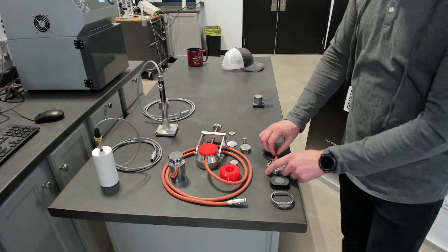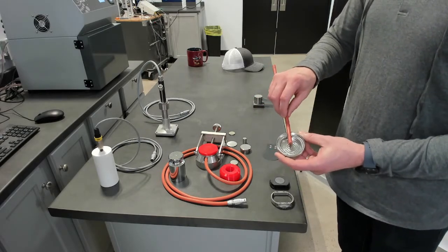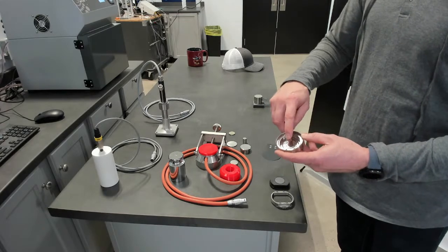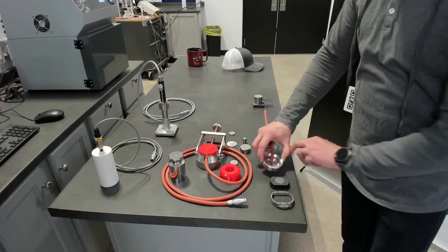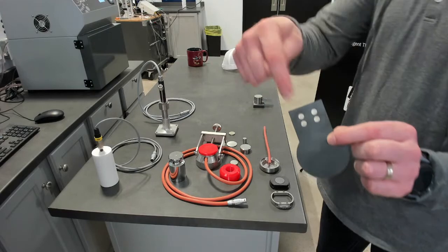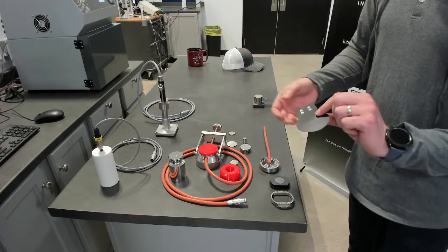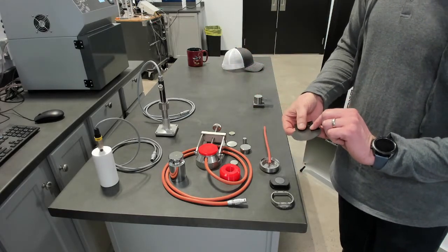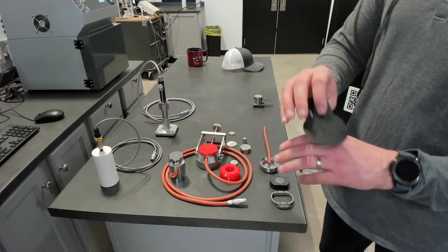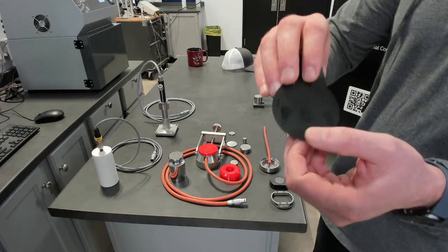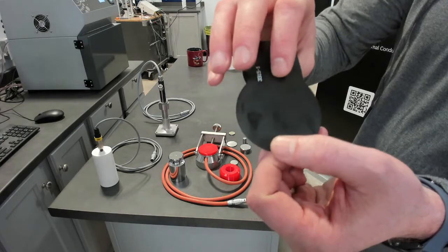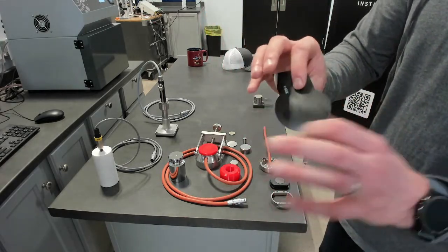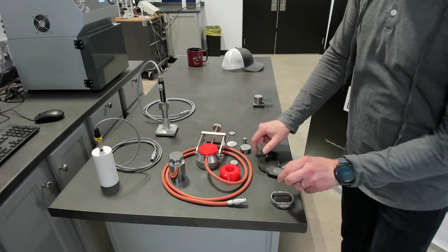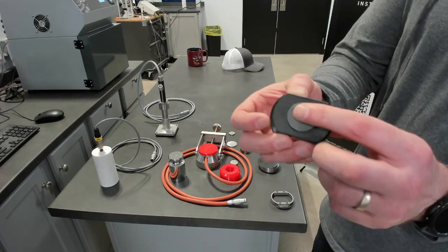So this is the body of the sensor itself, stainless steel with a wire. There are 4 contacts that are soldered to the back side of these 4 contacts, just like a cabled TPS sensor. This is a classic double spiral. It's a little hard to see in this light, but that's a double spiral sensor with extra Kapton. And what we use the extra Kapton for is to sandwich around this insulation.